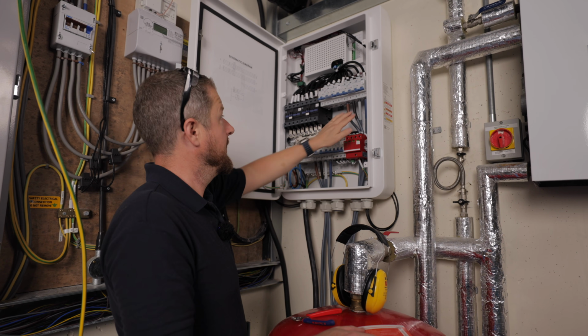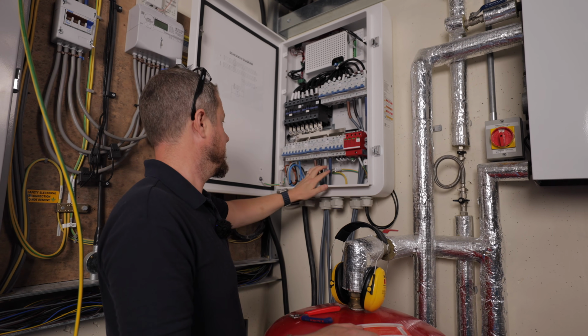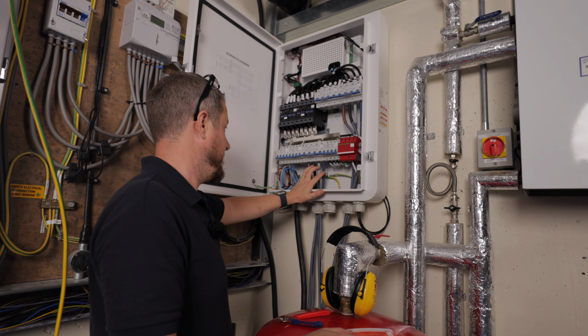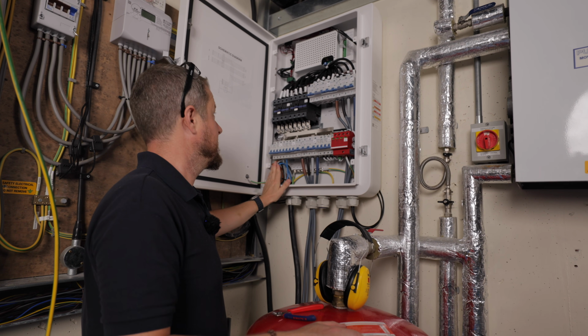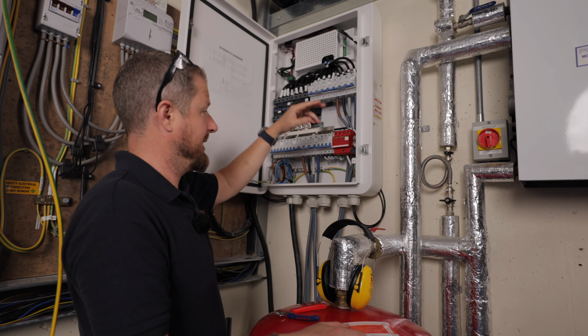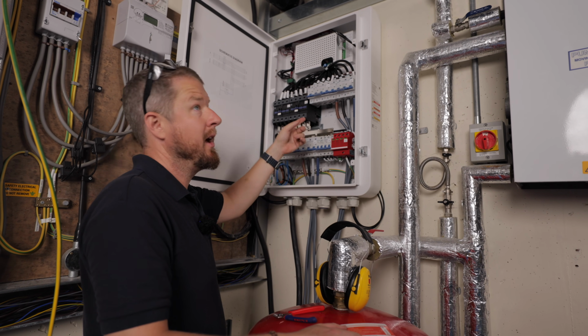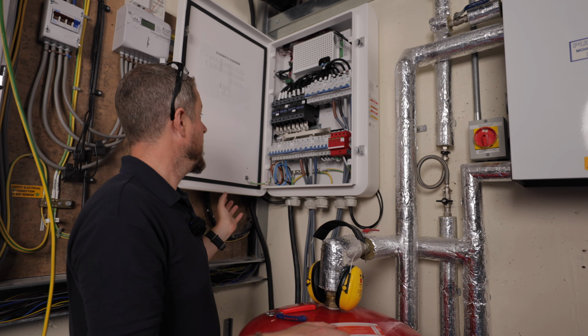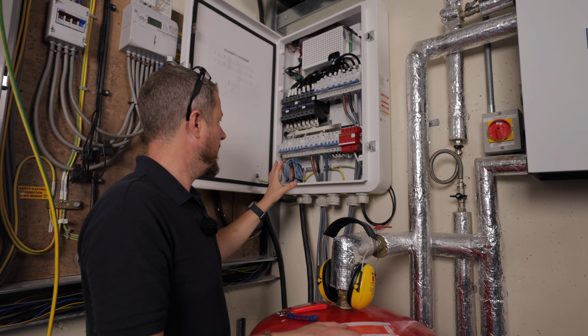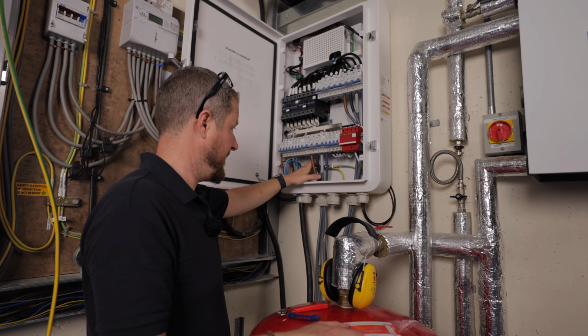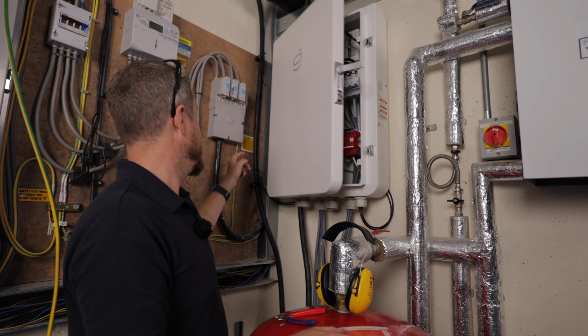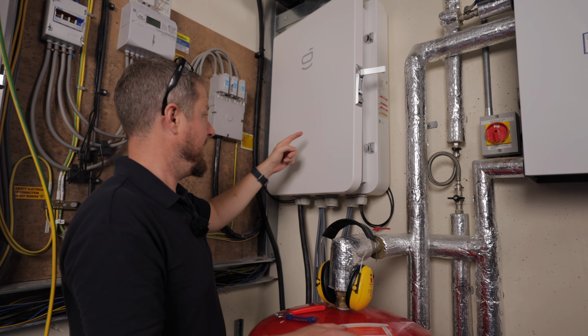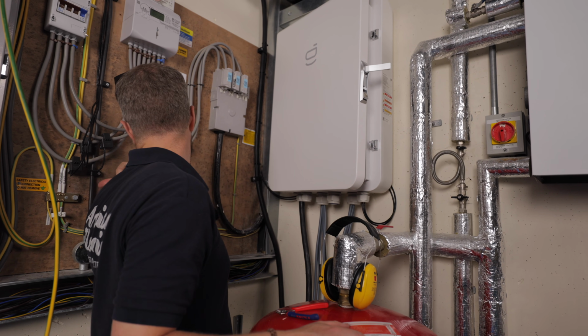So you've got the tails that go in from the grid, the tails that go out to the board for the backup. We've got the inverter circuit, and we've got the 2 data cables, one that goes to the inverter, one that goes to the BMS. So in here, it's basically wired up. We've just got a couple of earth wires to put in here as well, but that will be from the main earthing point here in, and then out to the main earth terminal there.